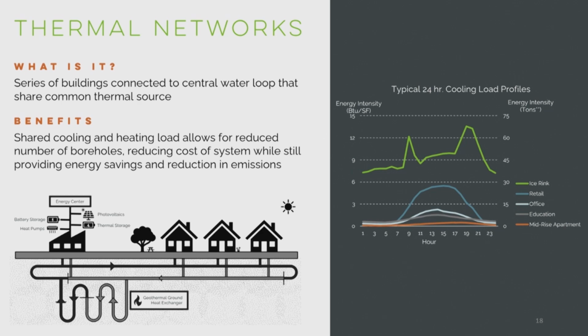So real quick, I'll touch on two technical concepts Dan alluded to earlier. The first is your load profiles throughout the day for each building. On the right you've got different building types and their typical load profiles for a day in July, showing that different buildings peak at different times throughout the day. That's a key concept as we're selecting buildings for these types of systems—ideally you want buildings that peak at different times, so your total system load is less than the sum of all individual building peak loads.